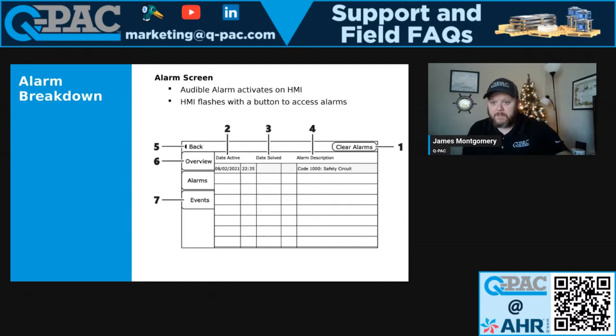When this sheet fills up, there's a little arrow. You can scroll up and down, and you can see what's an active alarm, red, no date solved, or a cleared alarm, date solved, green, right? So you can go back through. And events as well. When you switch that hand-off-auto switch from hand to off, from off to auto and vice versa, you'll get an event notification, and that'll be logged on the other page. But the overview is just going to give you the present stuff that's happening.